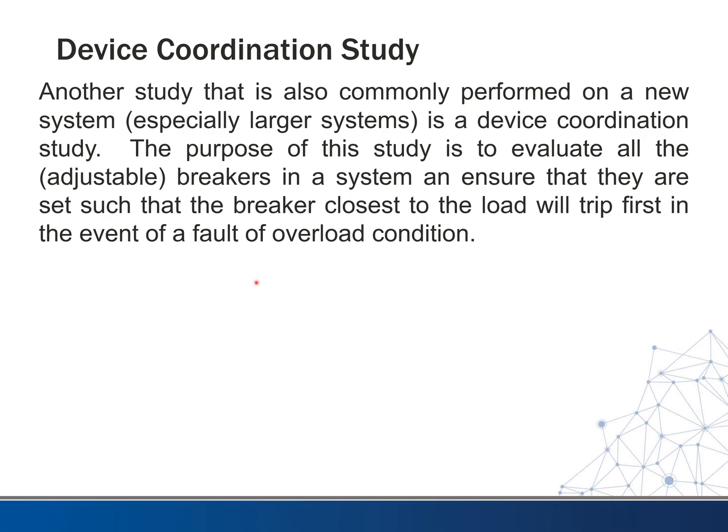The second type of study, usually done in conjunction with the first, is the device coordination study. This study is commonly performed on new systems, especially larger systems, and sometimes on smaller ones — it really depends on if you have adjustable breakers. The purpose of this study is to evaluate all the adjustable breakers in a system to ensure that the breaker closest to the load will trip first in the event of a fault or overload condition.